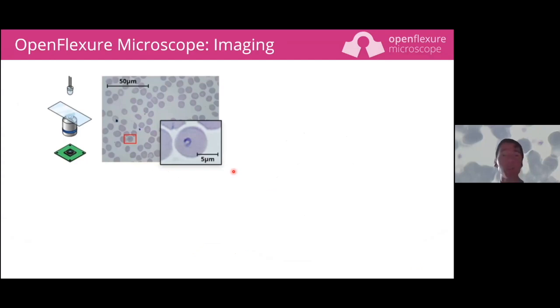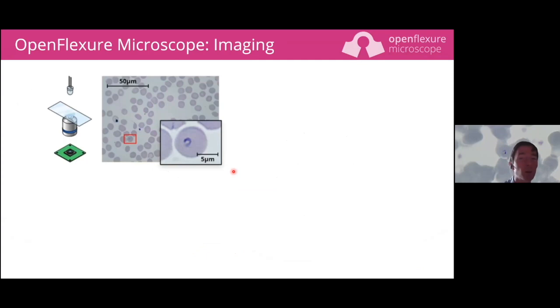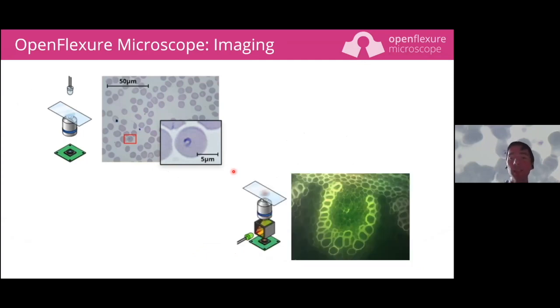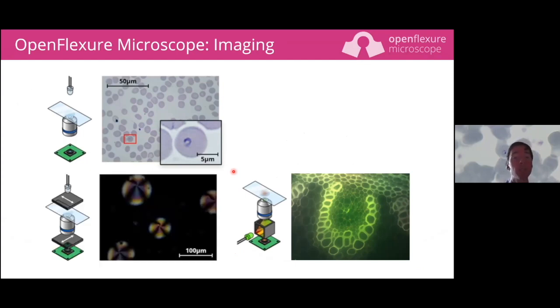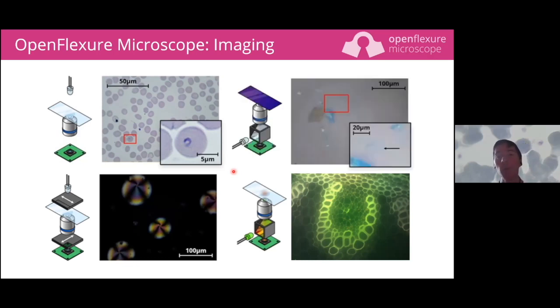It wouldn't be a talk about a microscope without showing some images - though actually the imaging capabilities of the OpenFlexure microscope are in many ways the least interesting part, because it's just a standard microscope with a regular objective. We can do bright-field imaging, stick in a beam splitter and do fluorescence - here's an epifluorescence image - swap in filter cubes for different channels, add polarizers, and even set it up in reflection to image graphene.